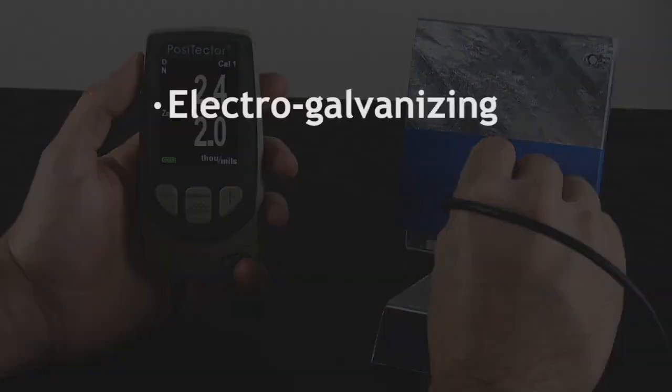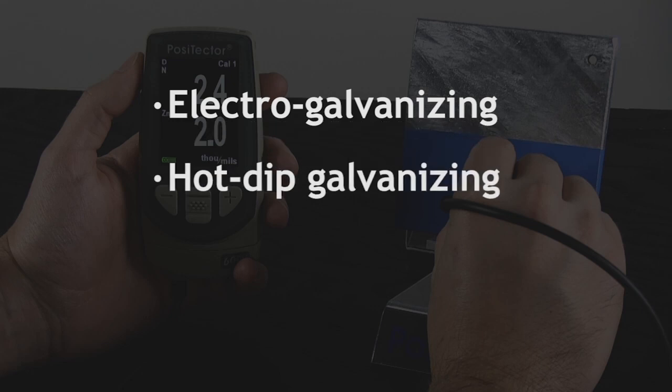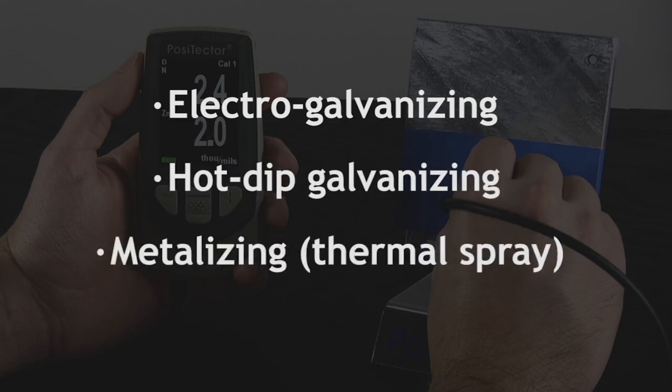The gauge will work with the three most common zinc application methods, provided the zinc layer measures at least half a mil or 13 microns.